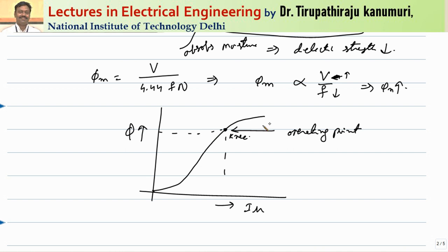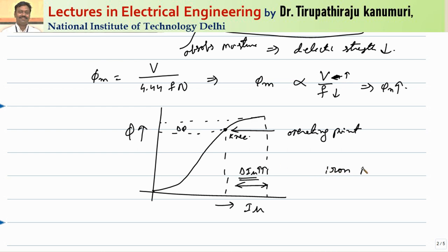When voltage increases or frequency decreases, the required flux increases. Even a small change in flux above the knee point causes a very large change in the magnetizing component — a huge magnetizing current is drawn from the supply, placing a heavy burden on the system. The iron losses, including hysteresis and eddy current losses, also increase due to increased voltage or decreased frequency. This phenomenon is called over-fluxing.